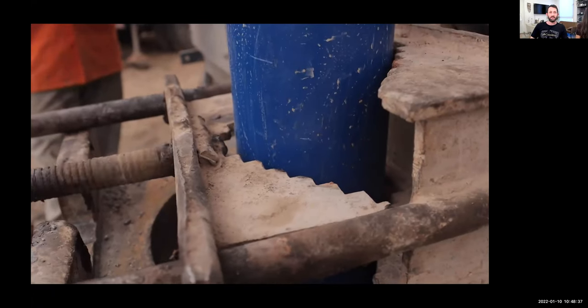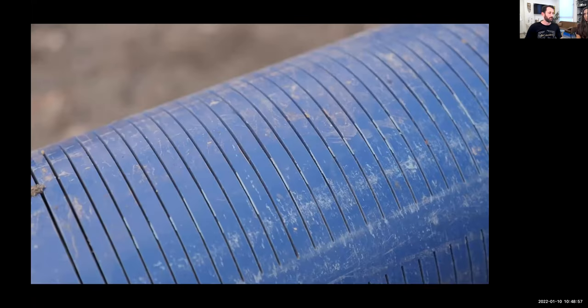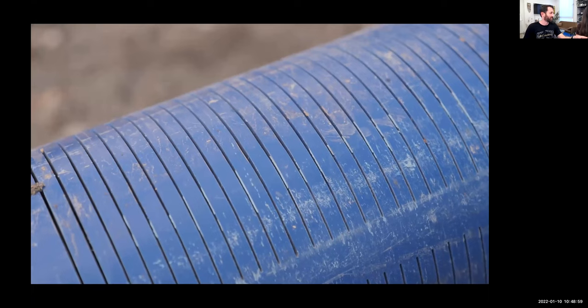So this is the plain casing at the start of the borehole. Normally we call it the dead storage, because it accommodates the settlement of the silt during drilling, which goes down to this plain casing at the start. Then after connecting that one, you connect the screen up to the level where you start striking the water aquifers.